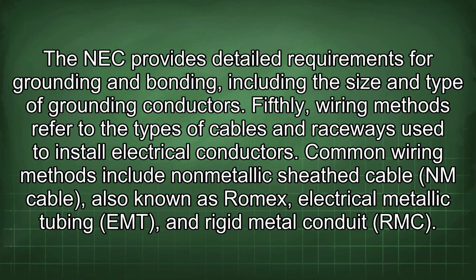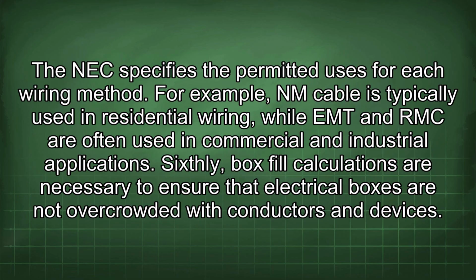Fifthly, wiring methods refer to the types of cables and raceways used to install electrical conductors. Common wiring methods include non-metallic sheath cable (NM cable), also known as Romex, electrical metallic tubing (EMT), and rigid metal conduit (RMC). The NEC specifies the permitted uses for each wiring method. For example, NM cable is typically used in residential wiring, while EMT and RMC are often used in commercial and industrial applications.